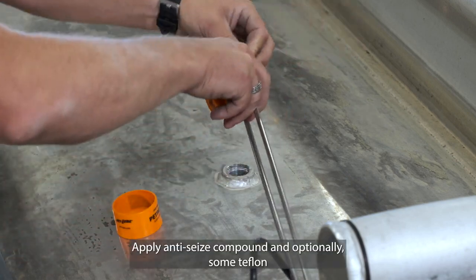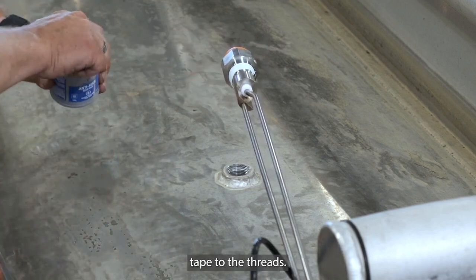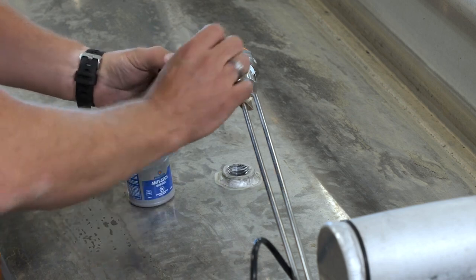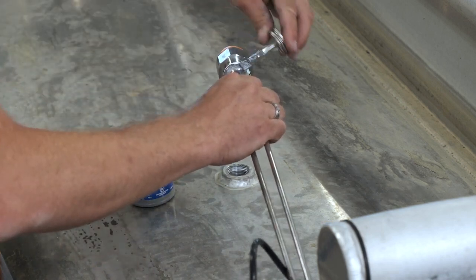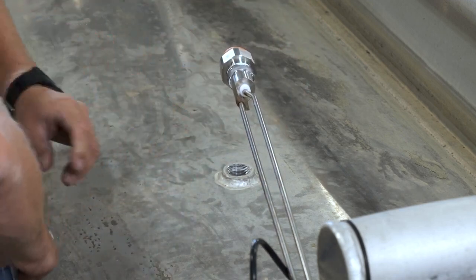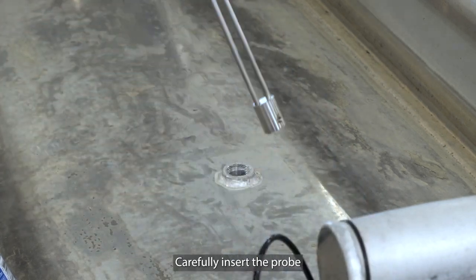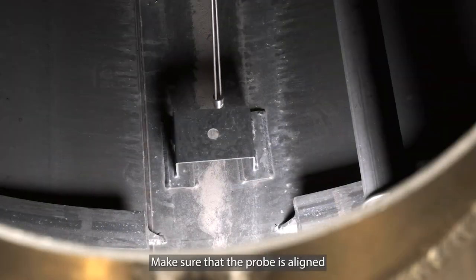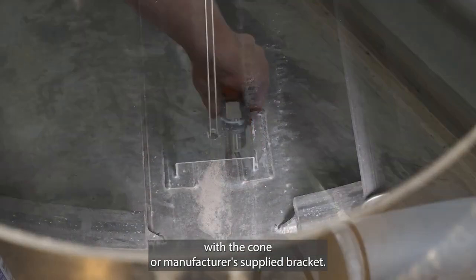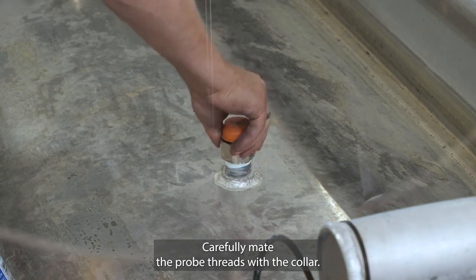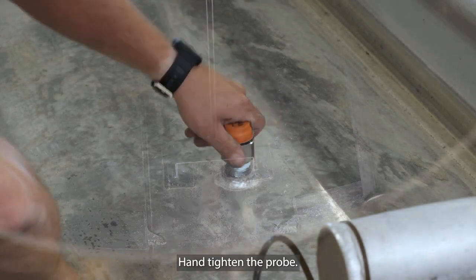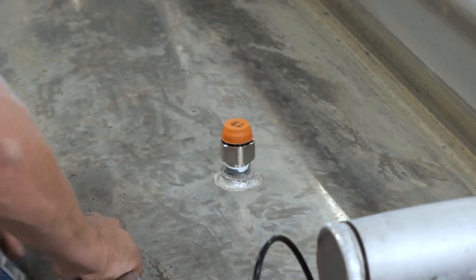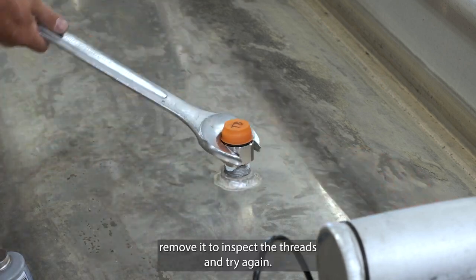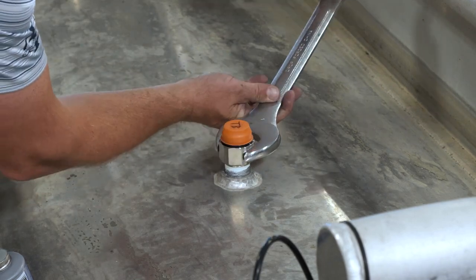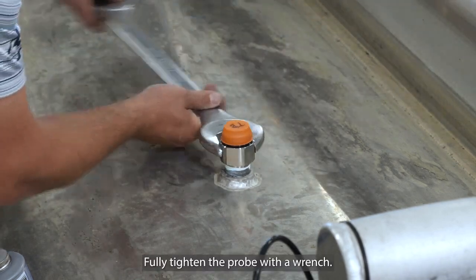Apply anti-seize compound and optionally some Teflon tape to the threads. Carefully insert the probe through the collar. Make sure that the probe is aligned with the cone or manufacturer's supplied bracket. Carefully mate the probe threads with the collar. Hand tighten the probe. If the probe binds while hand tightening, remove it to inspect the threads and try again. Fully tighten the probe with a wrench.